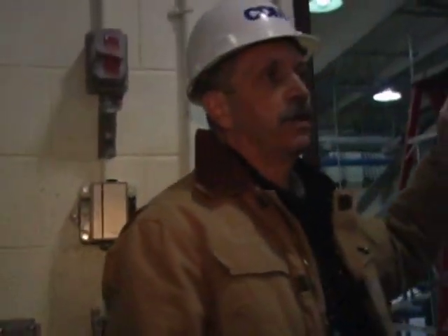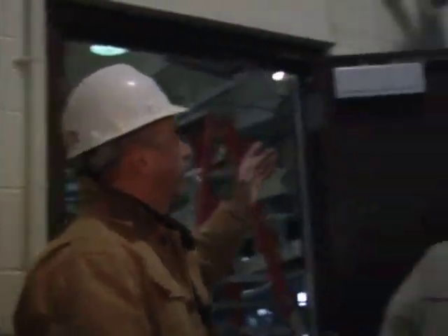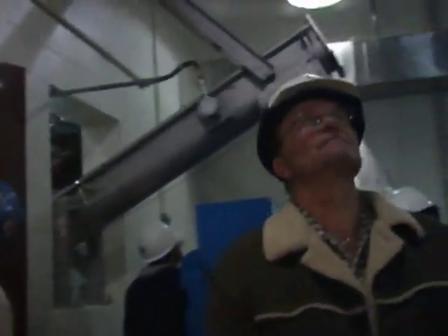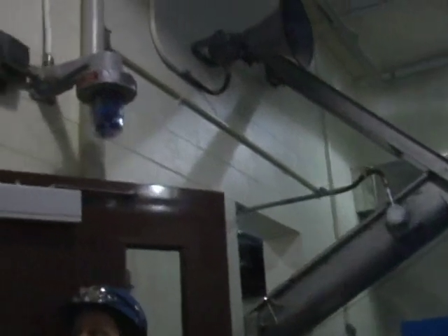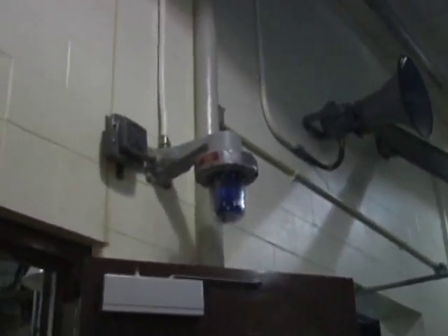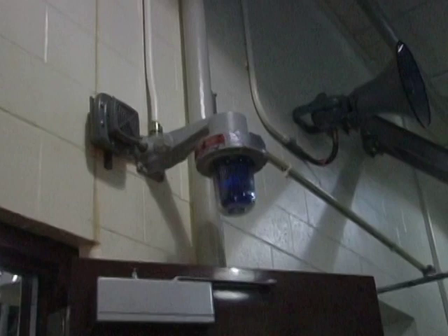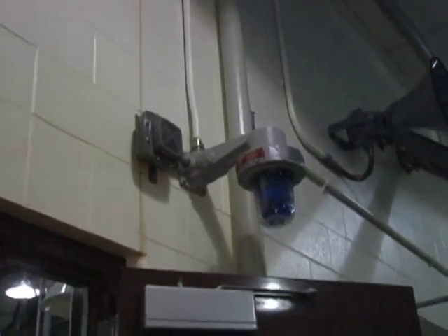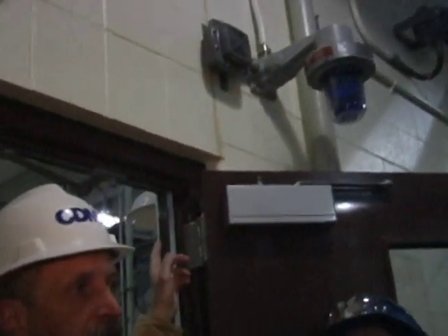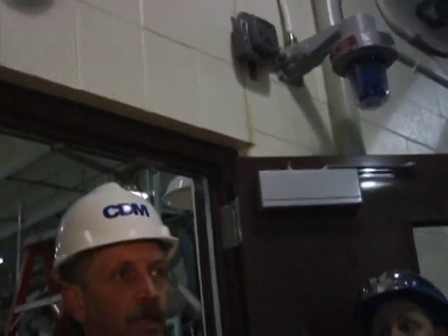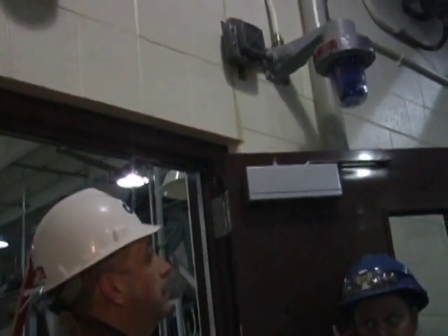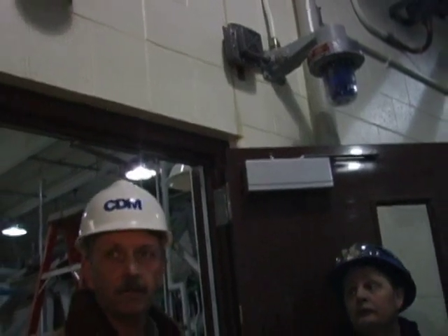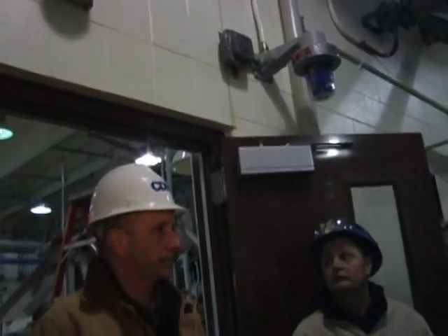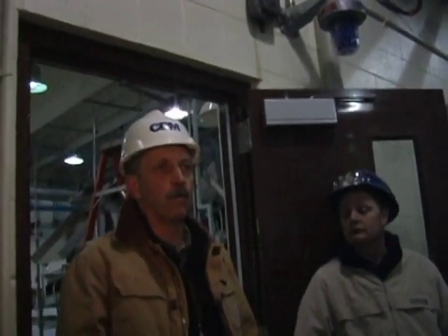The blue beacons are indication of a gas detection alarm. If you get either hydrogen sulfide or lower explosive limit detection within the building, the 6 units that are provided within the building itself are tied into that alarm system. You'll get a beacon as well as a klaxon, both inside and outside the building. There are three of the beacons on the outside of the building, one near each one of the entrances. So you're alerted to the fact that there may be a situation that you don't want to walk into.